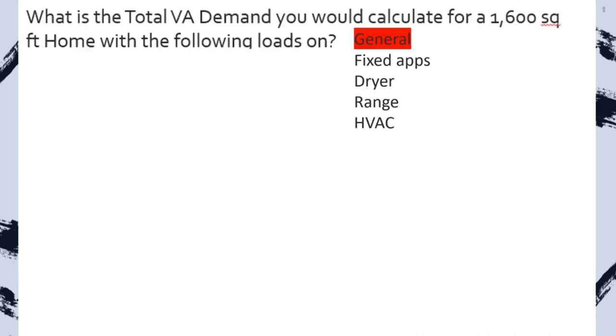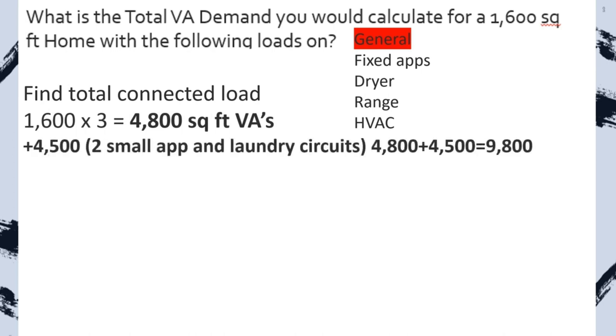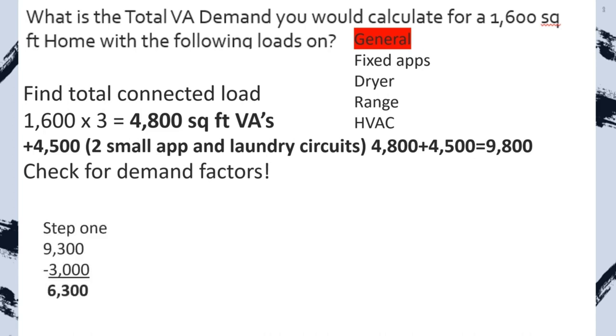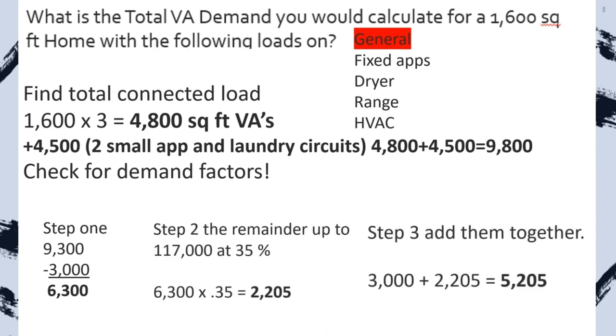Step one: find our general receptacle and lighting load. Total connected load: square feet multiplied by 3 VAs, then add 4,500 VAs for two small appliance and one laundry circuits, giving a total of 9,800. Check demand factors: take the first 3,000 at 100%, set it aside; multiply the remaining 6,300 by 0.35; add them back together for a new total reduced load of 5,205. Write that to our larger calculation.